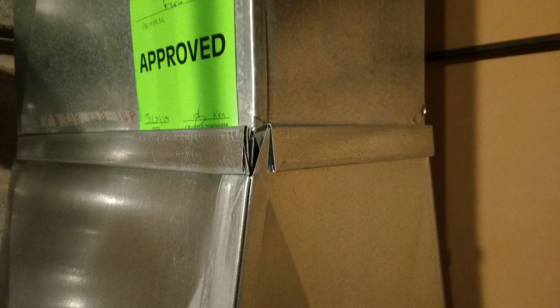Now, even on a new system, it may appear to be sealed, but HVAC contractors seal after the ductwork is in place. They almost have to, because the ductwork has to snake around immovable objects. So they seal after the ductwork is complete. Now the inspector may see all the tape on the bottom, but he can't really see the tops, nor can he see where the ductwork goes through walls. So how do you know if it's been sealed? Chances are it needs a little more sealing. Perhaps on the tops of the trunks where they're easy to get to, or maybe they can be sealed internally using a process or product called AeroSeal, and there likely are more interior seal systems available now. But AeroSeal is quite effective for sealing all those small leaks that you can't get to with tape and mastic.